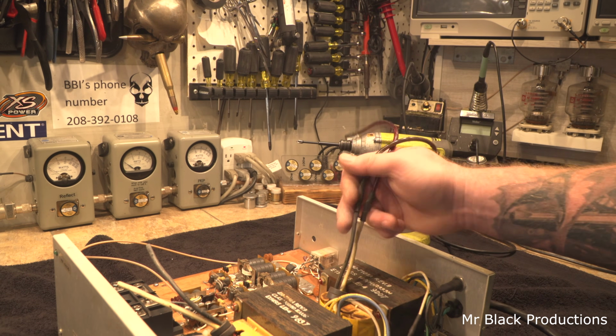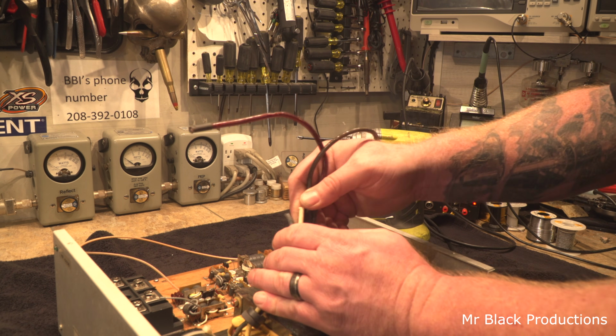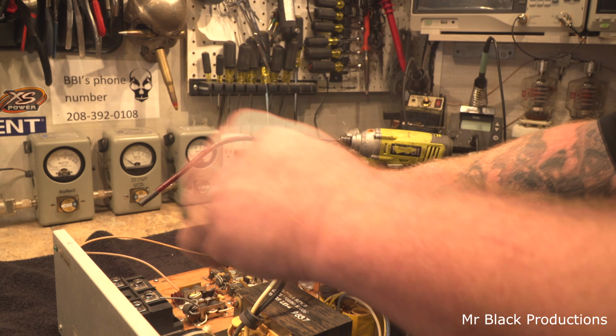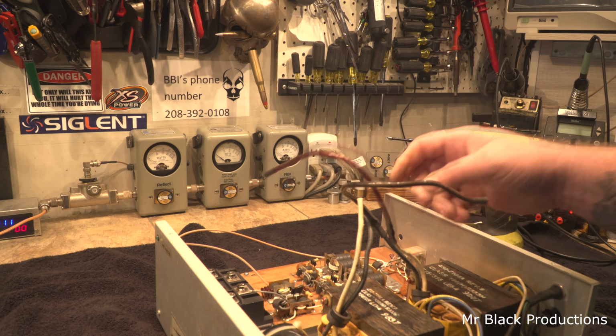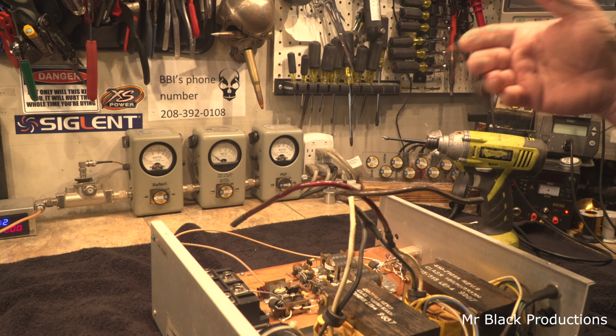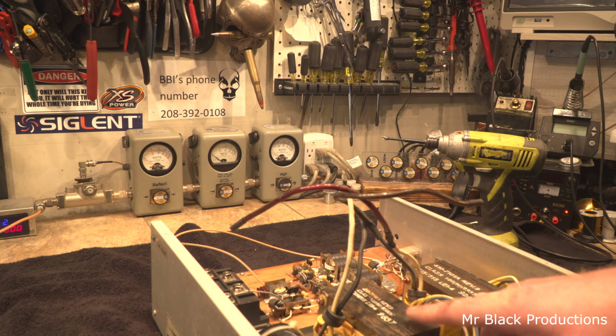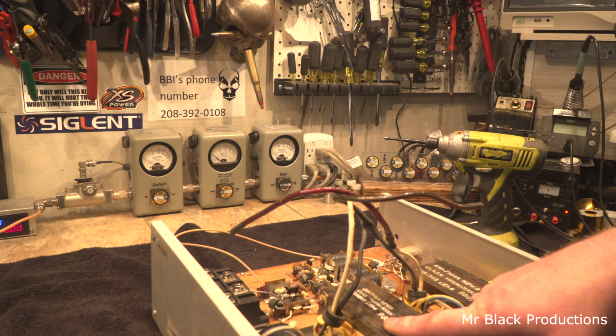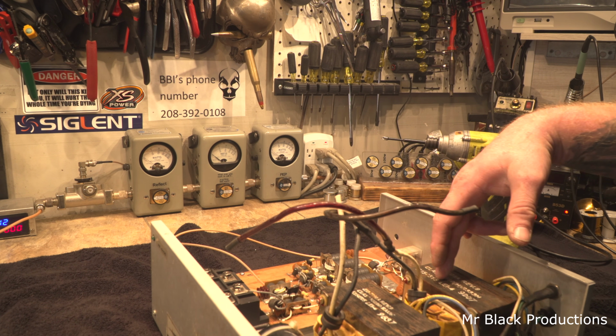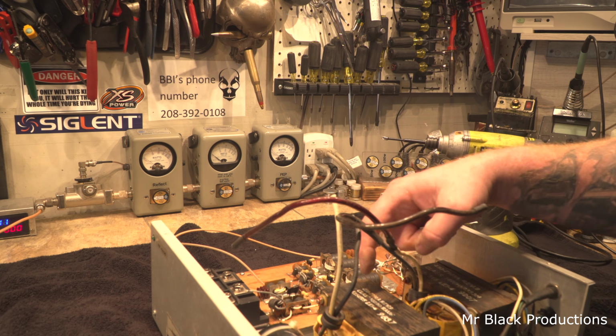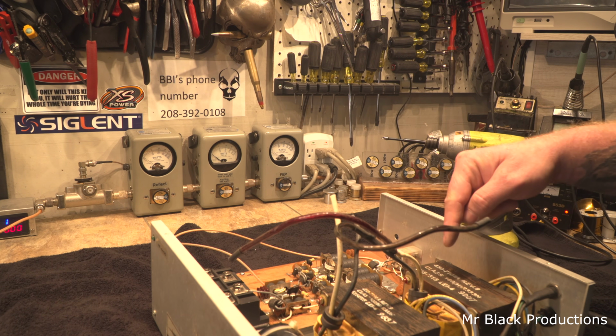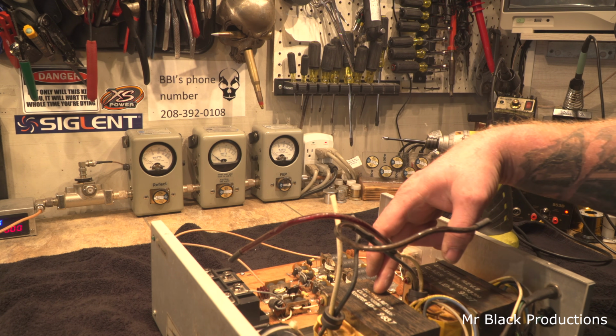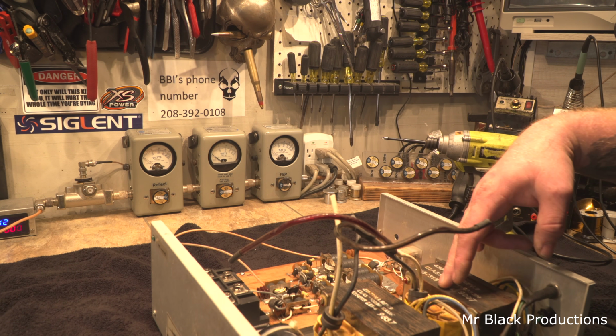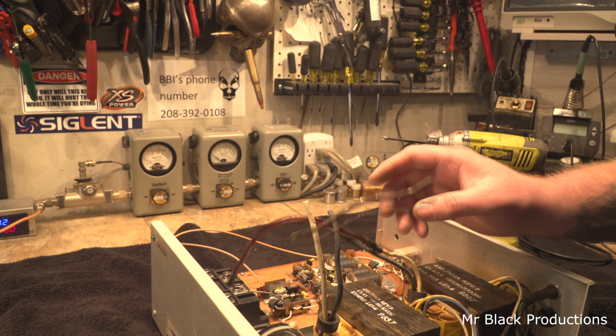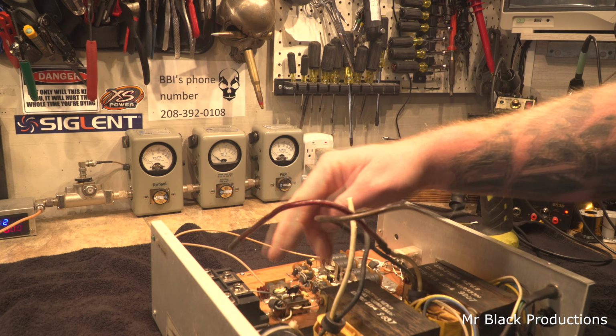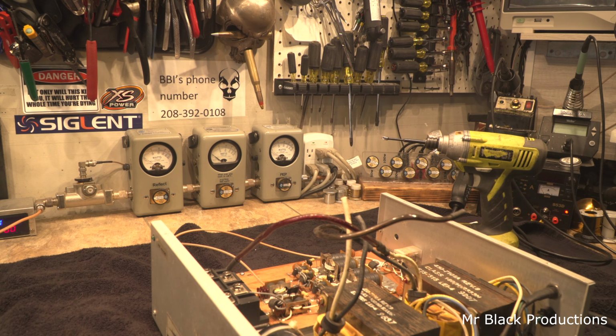The way this should be done is that these two leads need to be the same length. We sum these together at a larger piece of wire, then take that larger piece of wire over to our bridge. That way, when we key the mic and bring an electrical load onto our rectifier network, both transformers see an equal amount of current draw. If one is closer to the load and one is farther away, especially on the secondary side, the closer transformer will see 90% of the load and the other almost nothing. That means the closer transformer gets super hot and you see significant voltage drop, because the other one isn't doing anything until the first one can't give up any more amperage. So we have to sum these equally, then take it from that sum point to the bridge rectifier, so the current load can be equally distributed across both transformers.